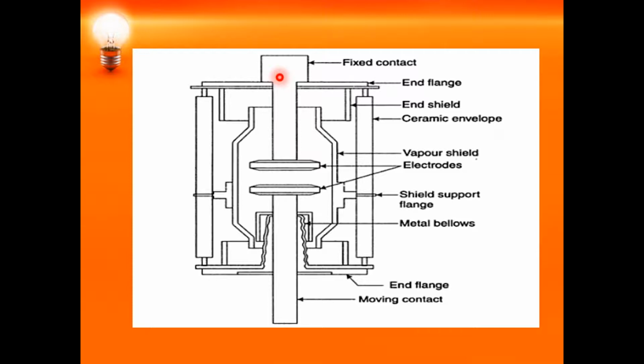The pressure inside this vacuum vapor shield is maintained around 10 to the power minus 4 to 10 to the power minus 6, which I have already told. The moving contact will move through a distance of around 5 millimeter to 10 millimeter depending upon the operating voltage, and the metallic bellows is usually made of stainless steel. The construction of this metallic bellows is very important because it decides the movement of the moving contact. Now coming to the working of this circuit breaker.